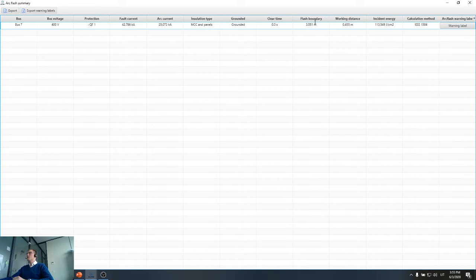So basically it's quite a huge distance, and maybe we will need to take some actions to reduce this flash boundary. Then working distance is estimated as 45 centimeters. This is a standard value, and we haven't changed it. And incident energy at the working distance is over 113 joules per centimeter square. So it means that this kind of energy will affect a person's skin if he works at 45 centimeters distance from the bus bar in case of the short circuit. It's actually quite a huge energy, and it will cause a high level of burn.